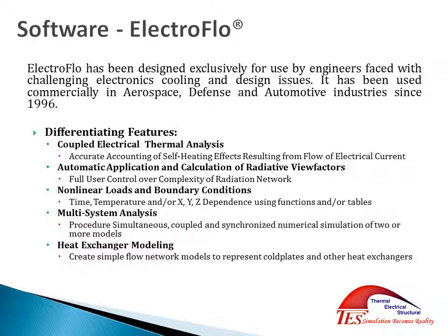Looking here at some of the differentiating features, coupled electrical thermal analysis is one of our critical features, and we'll talk in quite some depth about that later. We have an automatic application and calculation of radiative view factors using a patented approach that allows you to quickly have a radiative network. All boundary conditions can be applied non-linear loads using both tables and functions. We have a multi-system analysis approach, which allows you to have completely separate systems modeled together where they're coupling. So say you have a rack system, you could have several different electronics boxes all be modeled in different models, and then that coming together. And finally, we do have heat exchanger modeling.